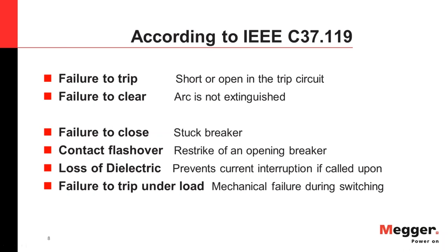Starting with what is Breaker Failure. According to IEEE C37.119, which is a standard for Breaker Failure Protection, breaker failure is categorized into several types. The first two are Failure to Trip and Failure to Clear. According to the standard, these two are called Breaker Failure. The rest of them can lead to a Breaker Failure, but they are not categorized exactly as Breaker Failure.